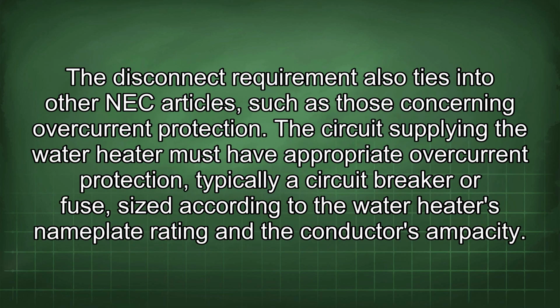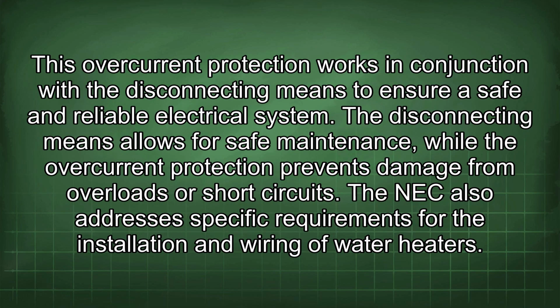The disconnect requirement also ties into other NEC articles, such as those concerning overcurrent protection. The circuit supplying the water heater must have appropriate overcurrent protection, typically a circuit breaker or fuse, sized according to the water heater's nameplate rating and the conductor's ampacity. This overcurrent protection works in conjunction with the disconnecting means to ensure a safe and reliable electrical system. The disconnecting means allows for safe maintenance, while the overcurrent protection prevents damage from overloads or short circuits.